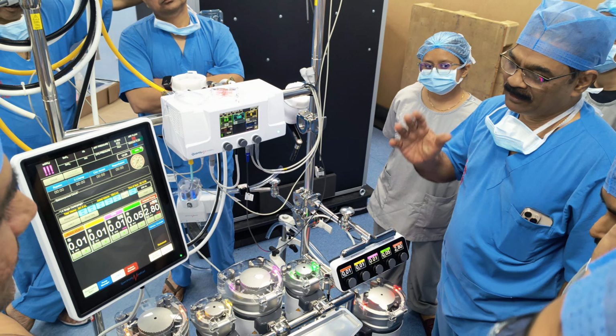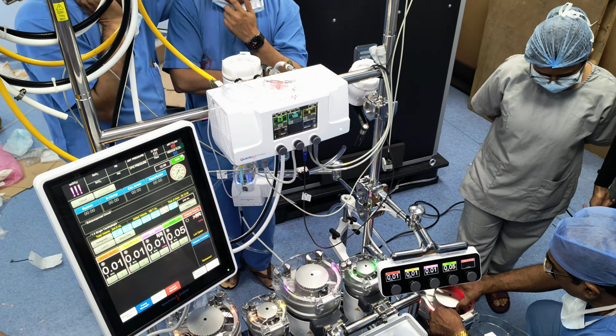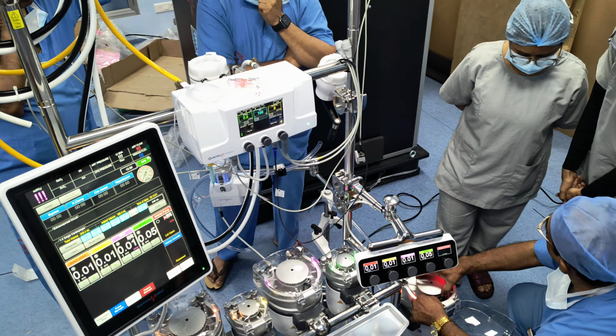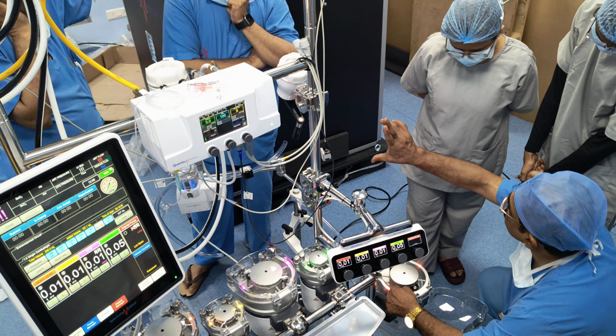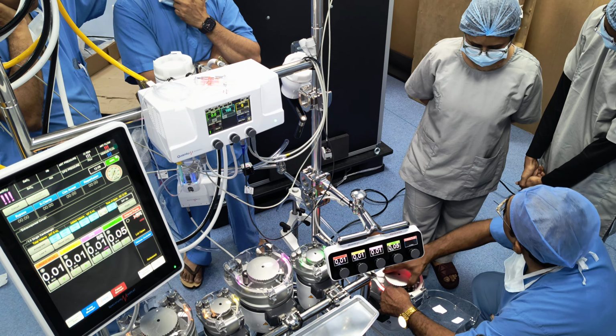You put it off. Open the pump, hold it here. So clockwise, tighten the occlusion, anti-clockwise to release it. So you see your line, the level is dropping, or the pressure is.